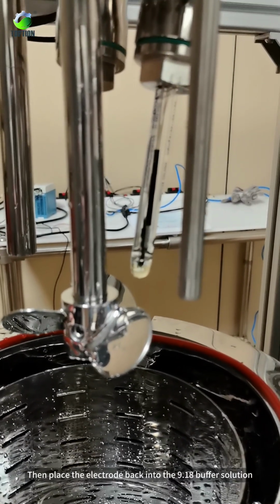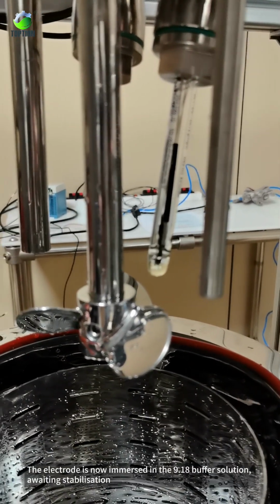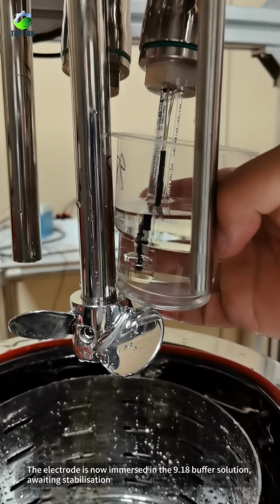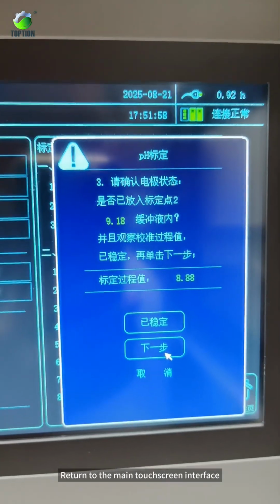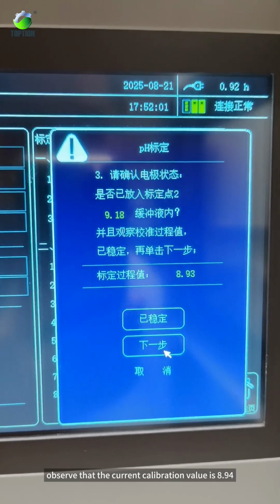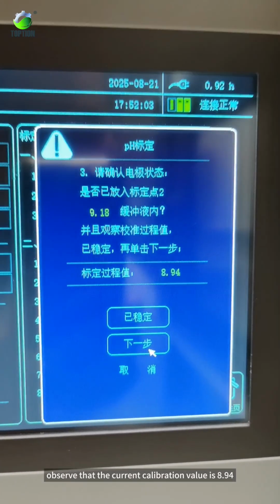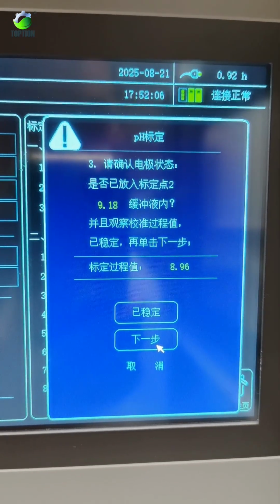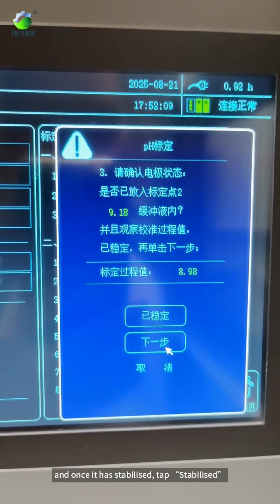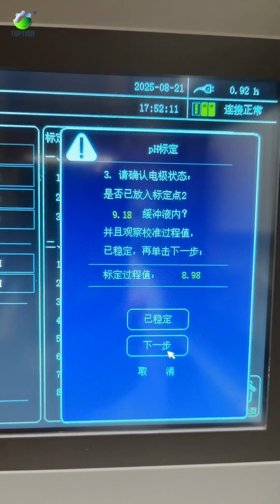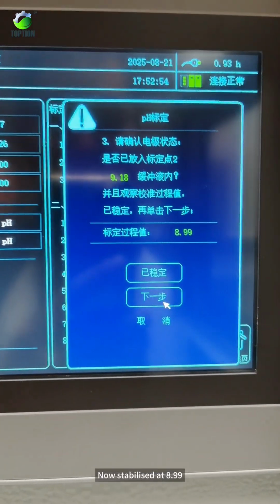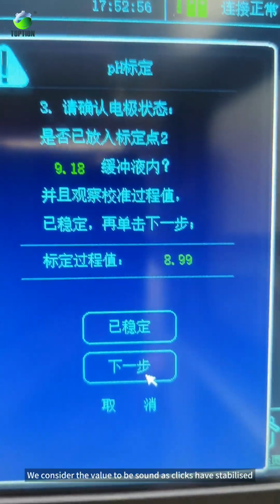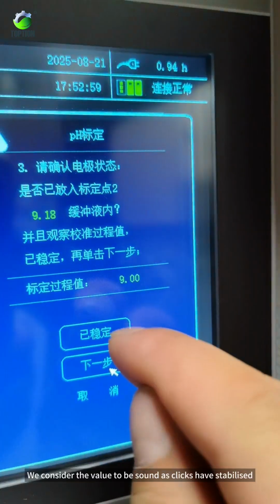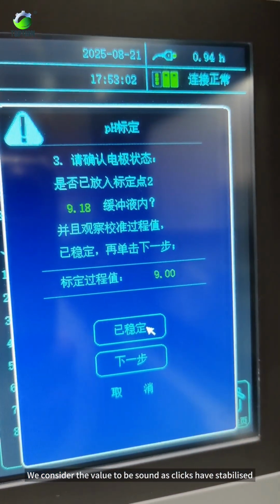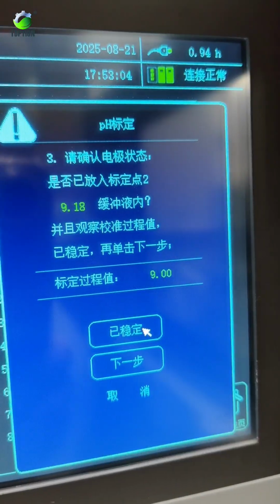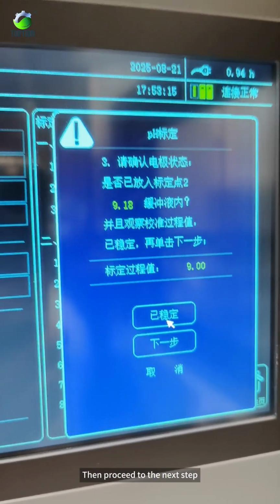Then place the electrode back into the 9.18 buffer solution. The electrode is now immersed in the 9.18 buffer solution. Awaiting stabilization, return to the main touchscreen interface. Observe that the current calibration value is 8.94. And once it has stabilized, tap Stabilized. Now stabilized at 8.99. We consider the value to be sound as it has stabilized. Then proceed to the next step.